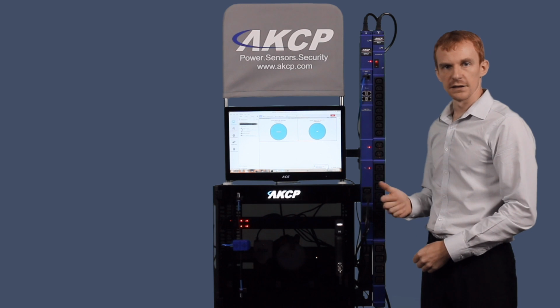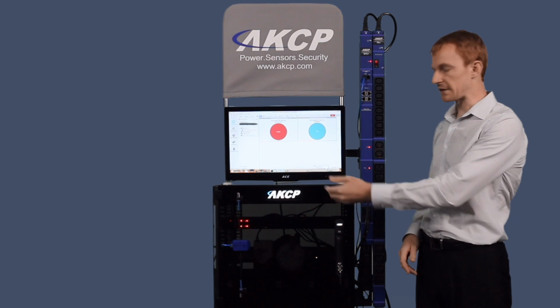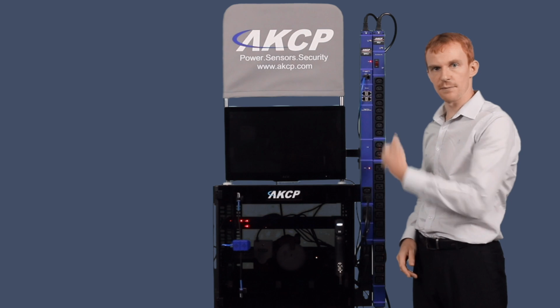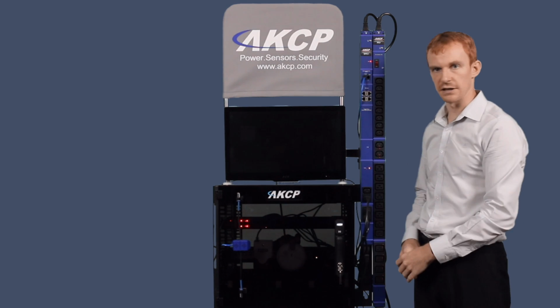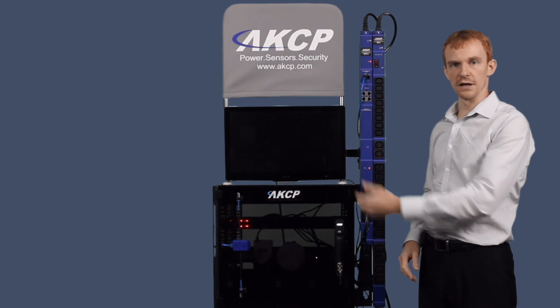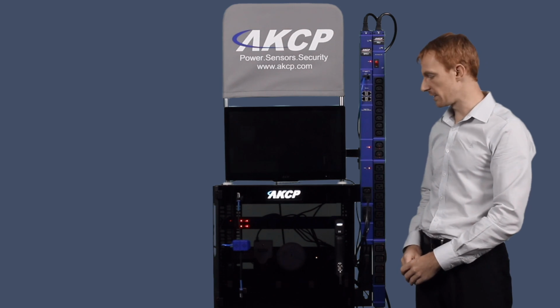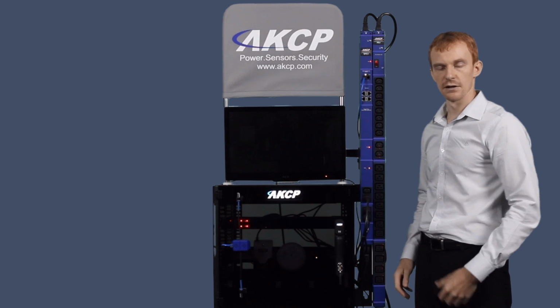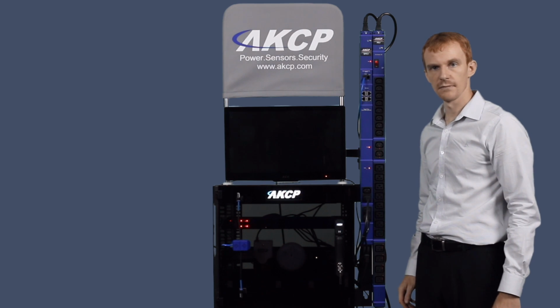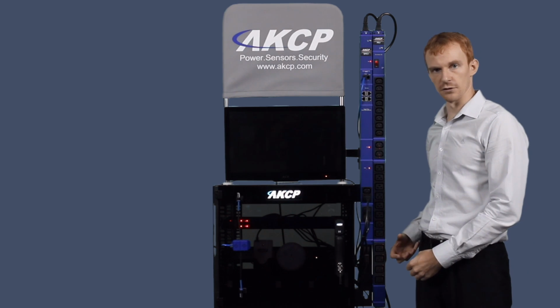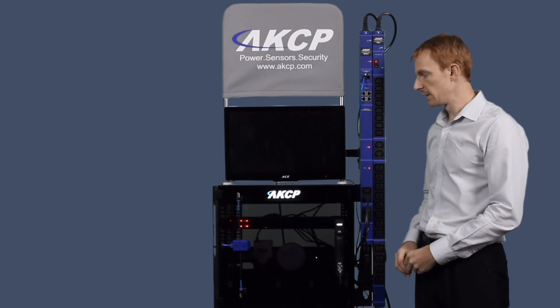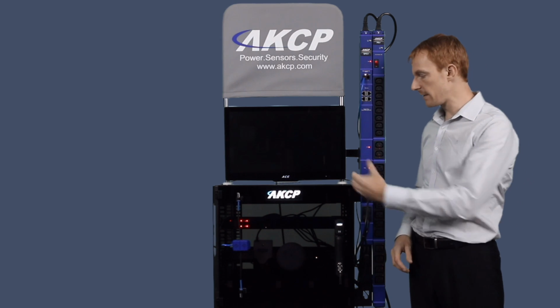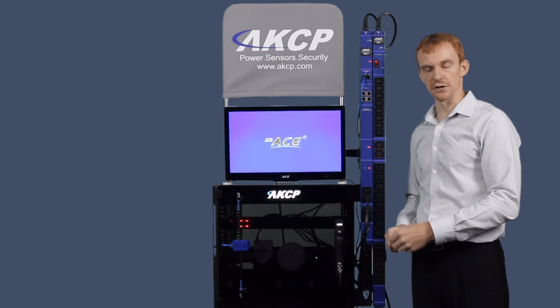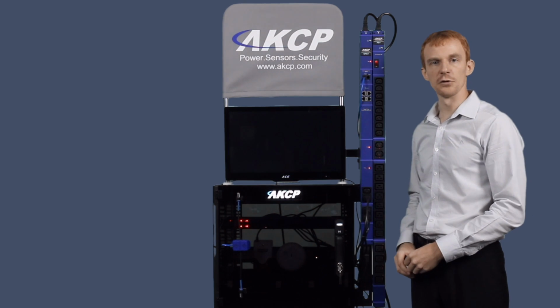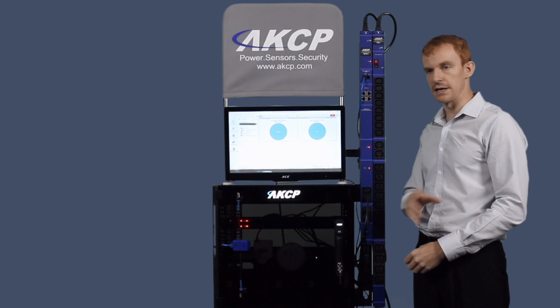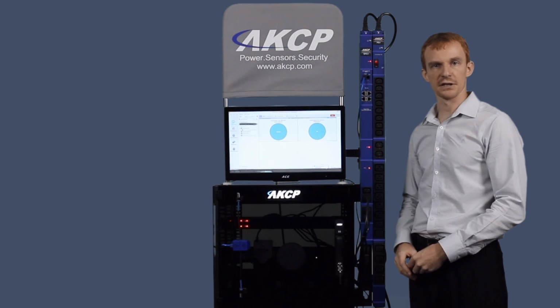In the event of a fire, the smoke alarm will sound, and once the system detects a critical condition, the main power relay will go off, bringing down the power to the cabinet. Once the smoke detector returns back to a normal condition, power will be restored and everything will come back on. AKCP also offers an optional in-cabinet gas suppression system that can work together with this, so in the event that cutting the power is not enough, we can also release gas but contain it to within the cabinet only. Again, no need to flood the whole data center with dangerous gases.